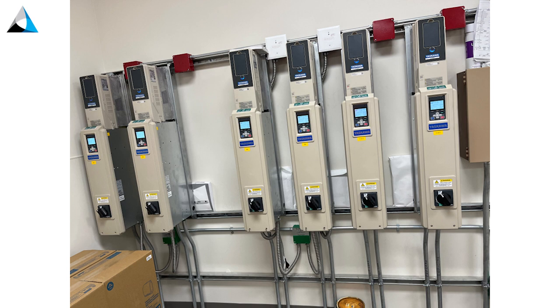These VFDs — what type of room in this hospital do you think they're located in? A storage room, because somebody thought they could put the VFDs on the roof, then realized they shouldn't because they're not NEMA rated, so they commandeered a storage room. That's one of my pet peeves — spaces get commandeered for MEP equipment because somebody didn't plan well enough for where things should go.